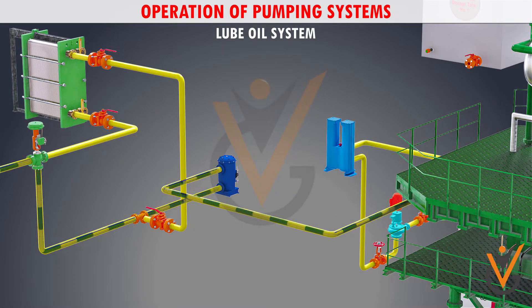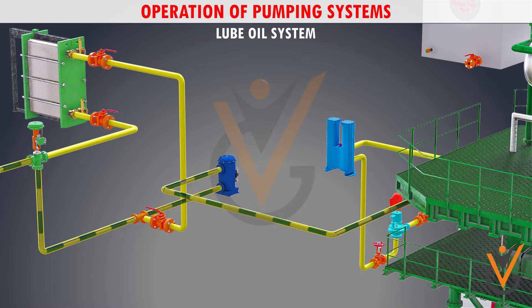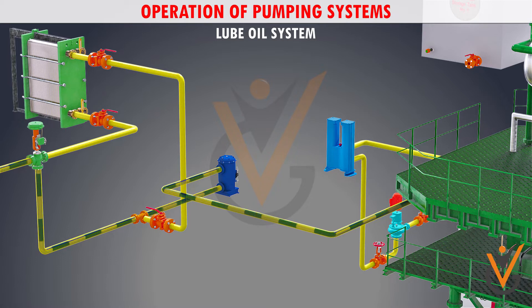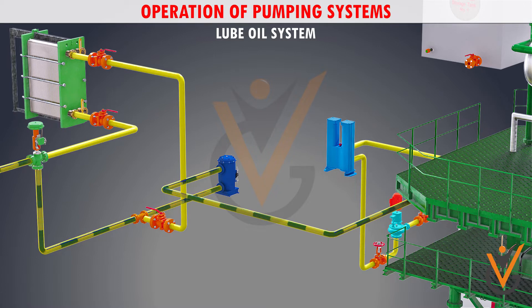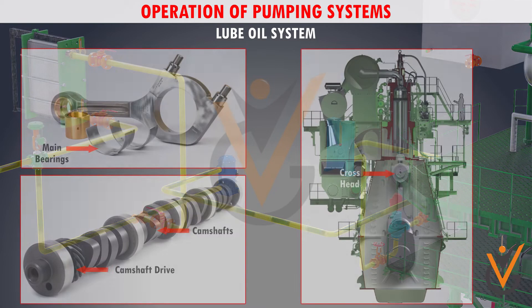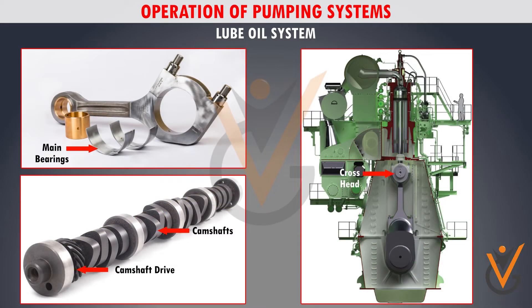An automatic backflushing filter unit with a magnetic core helps to remove any metal debris. The supply pressure in the main lubrication system depends on the design and requirement and is generally around 4.5 bars. The main lube oil system supplies oil to the main bearings, camshaft, and camshaft drive.